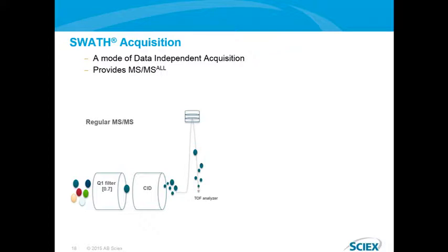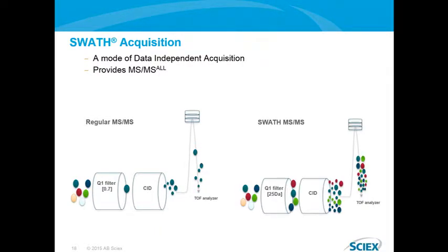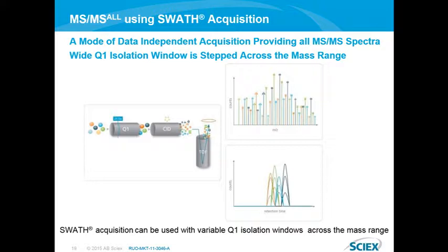It allows sequential acquisition of MS-MS of all precursor ions across a specified mass range by dividing the mass range into small windows. In every scan cycle, the instrument rapidly and sequentially acquires MS-MS of all mass windows across the specified mass range.